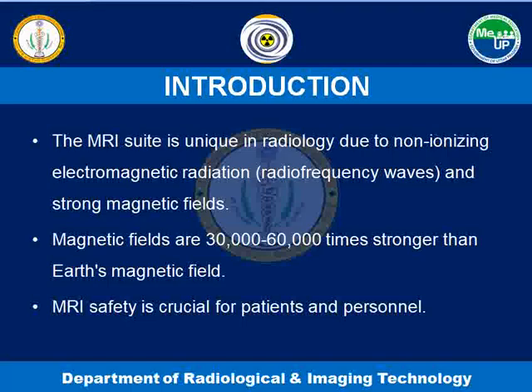Introduction. The MRI suite is unique in radiology due to non-ionizing electromagnetic radiation and is generally a safe way to take pictures of the inside of the body, especially for young women. However, there are some short-term risks associated with this, including magnetic objects becoming projectiles if they are inadvertently brought into the scanner room, as magnetic fields of MRI scanners are 30,000 to 60,000 times stronger than Earth's magnetic field. Tissue heating from RF pulses. Peripheral nerve stimulation from magnetic field gradients.